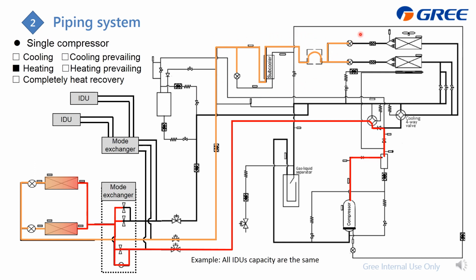The refrigerant will get expanded at this outdoor heating EXV, and then become low pressure and temperature liquid, then absorb heat from this outdoor heat exchanger and become gas, and get through this four-way valve, and then back to the gas liquid separator, and then to the compressor.